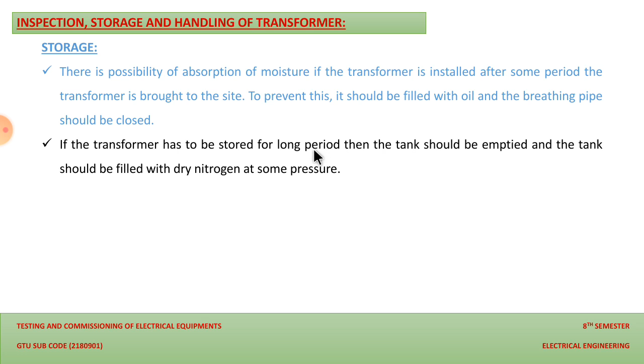So yes, by keeping in mind the pressure of the nitrogen according to the strength of the transformer winding and other utilities present inside the transformer, we can fill it with dry nitrogen so that we can protect it from the absorption of moisture and certain damages. And the transformer should be covered if it is stored in the open, to keep out moisture, dust, etc. So we can protect our transformer by closing it with proper utilities. So do not enter inside the tank.